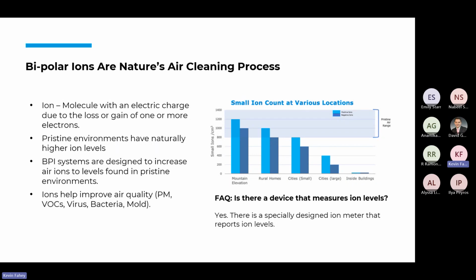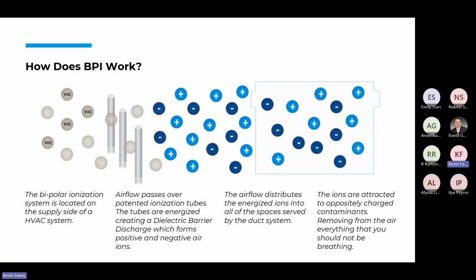So what we do is we help engineers design an equipment selection that will increase the ion levels to what you would find in a more pristine outdoor environment of 800 to 1,500 ions per cubic centimeter. So how does it work? This is considered an active air cleaning process. Active meaning we put these tubes on the supply side of an air system. They could go in the discharge plenum of an air handler. They could go in the main supply ducts before they branch. They're downstream of coils and filters, so that they're the last thing before the air hits the ductwork and then gets into the occupied environments.